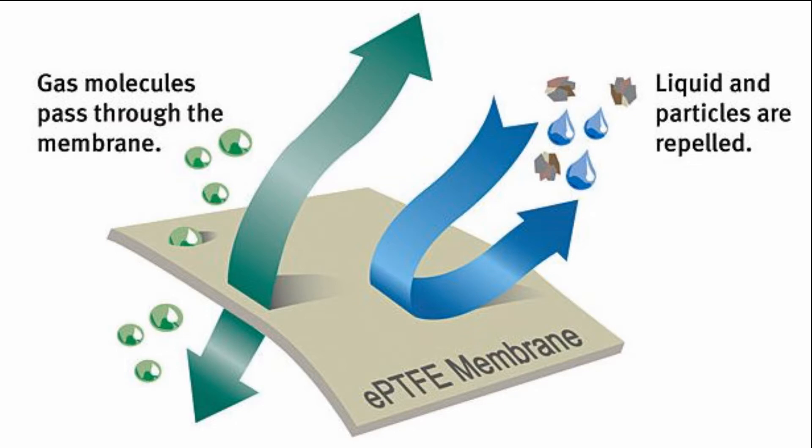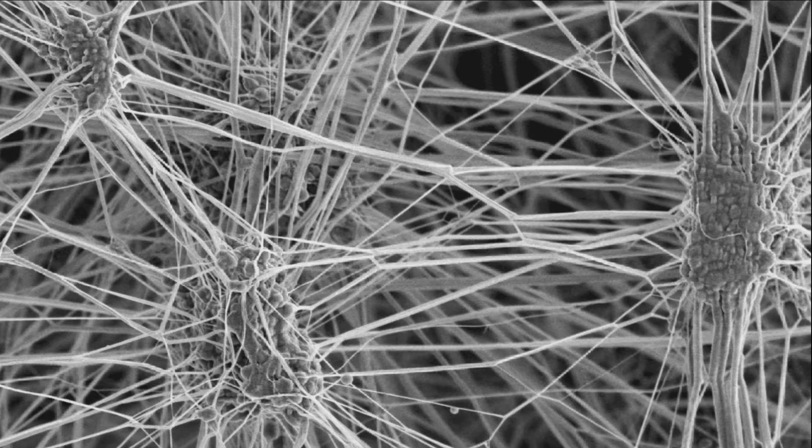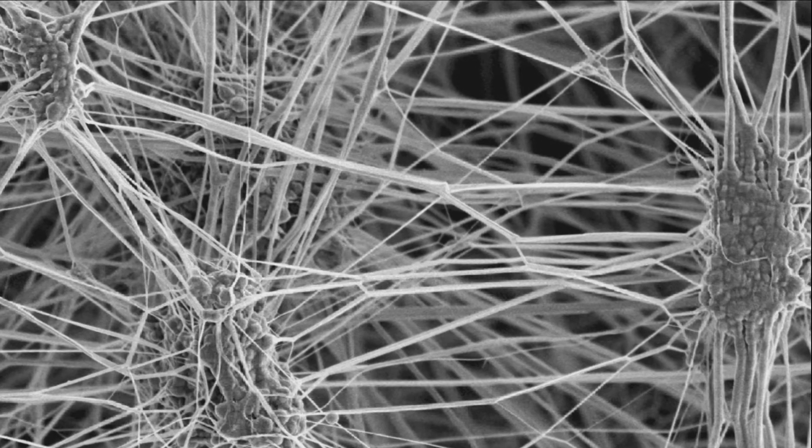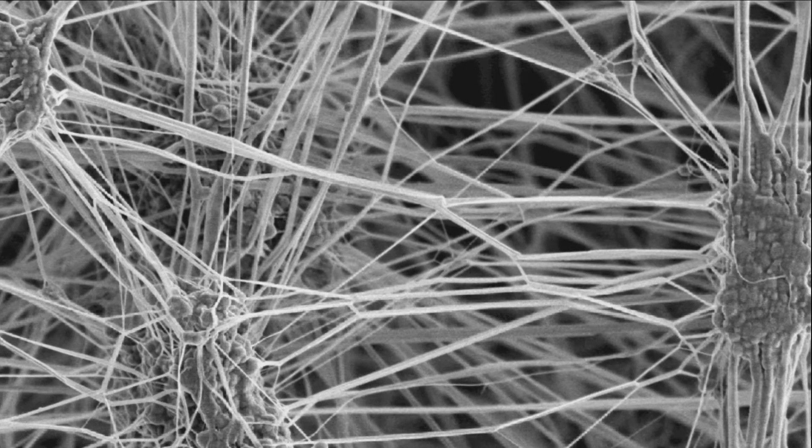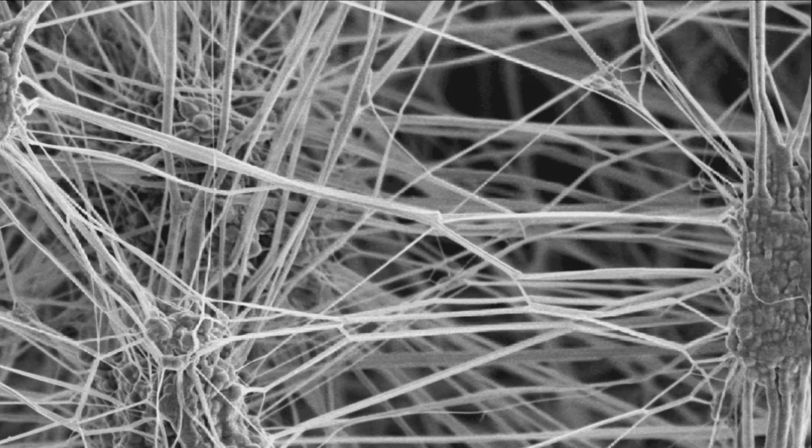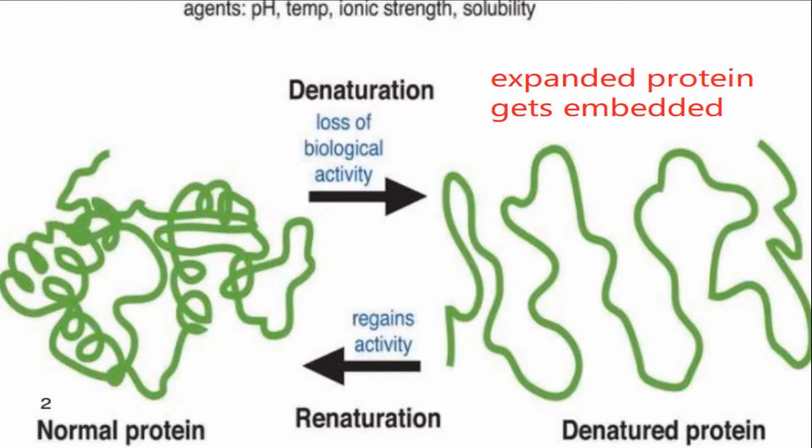For a time, this new ePTFE channel worked effectively, but eventually led to new issues when these channels were exposed to decontaminating agents that removed the proteins that were embedded in the channel matrix. These proteins slowly ate away at the channel, thus leaving microscopic holes in the walls of the channel.